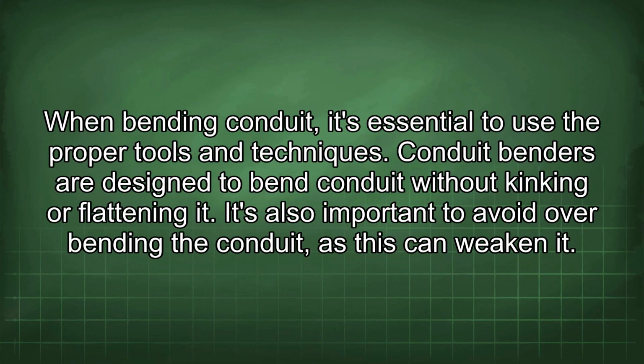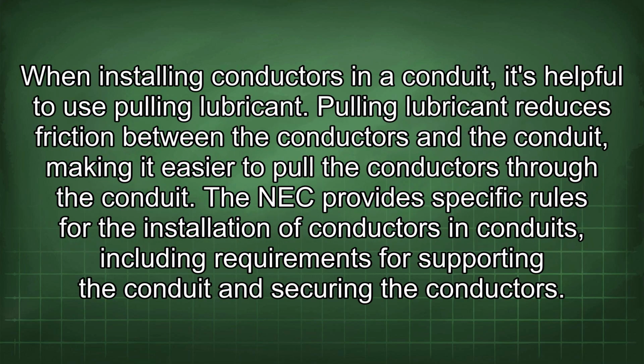When bending conduit, it's essential to use the proper tools and techniques. Conduit benders are designed to bend conduit without kinking or flattening it. It's also important to avoid overbending the conduit, as this can weaken it. When installing conductors in a conduit, it's helpful to use pulling lubricant. Pulling lubricant reduces friction between the conductors and the conduit, making it easier to pull the conductors through the conduit.